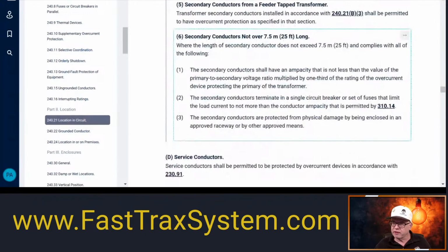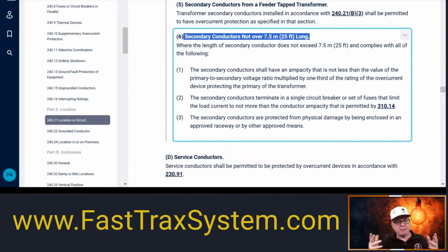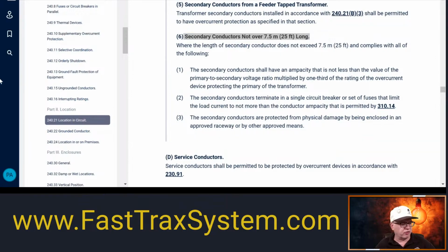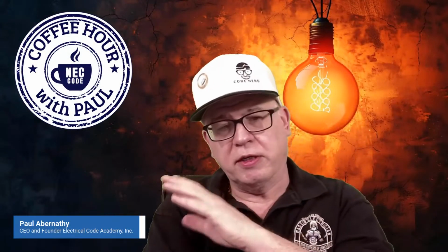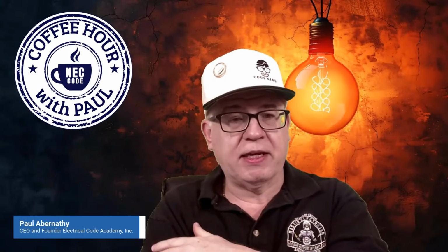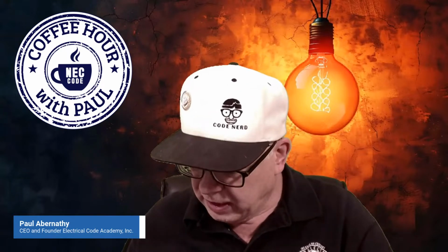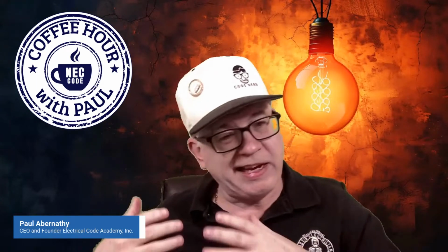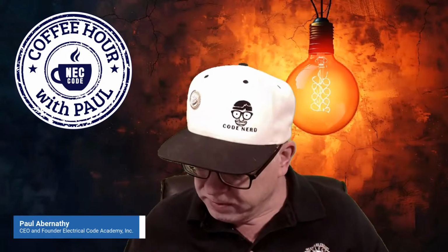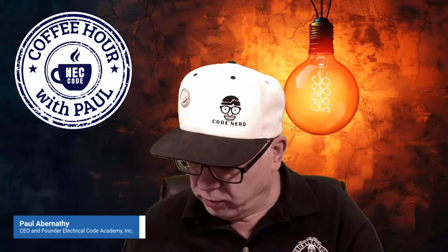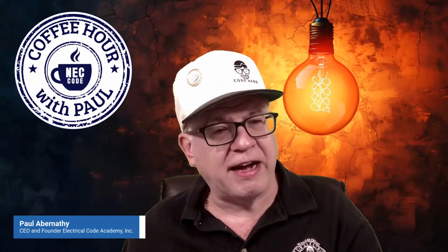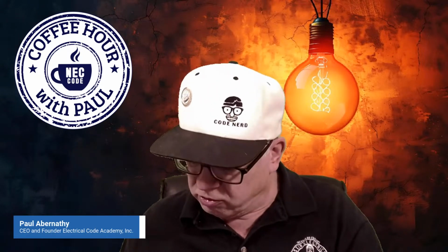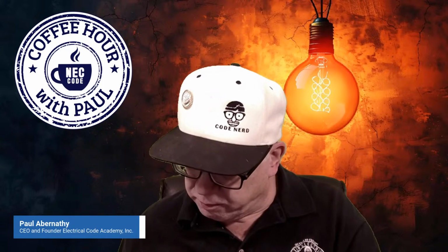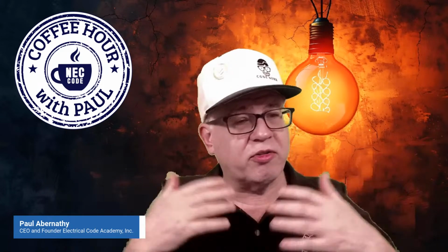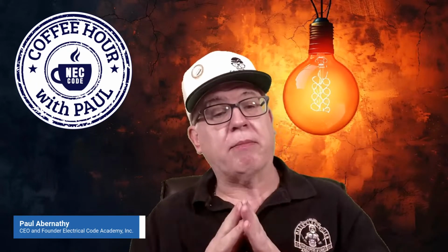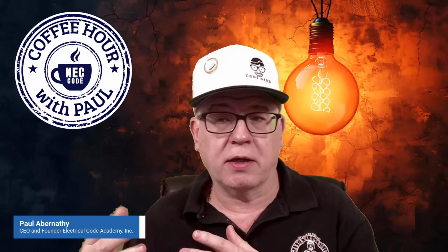Now I will say for this 25-foot, a lot of this is also going to be dictated by whatever my load calculation is. So if you're the engineer designing this, you're going to be picking a transformer because you know what your loads are going to be. So if I'm picking a 75 kVA transformer, and I'm trying to find the output amps at the secondary, since it's a 208, we know to go 208 times 1.732, which is the square root of 3, and that gives me 360.256. So let's say 360.26. I'm going to take that 75,000 and divide it by 360.26. And you could just use 360, which is close enough in the field. That is 208 amps. So I'm probably going to be terminating this into a 200 amp panel with a main breaker.